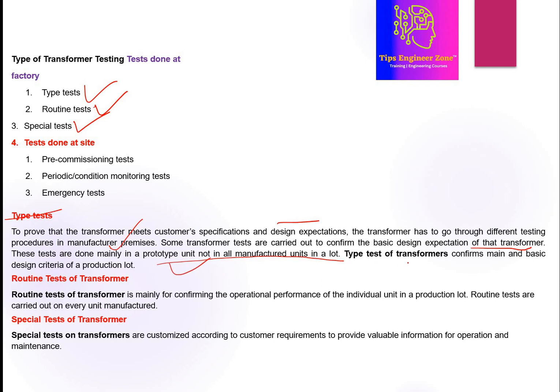A type test on a transformer confirms the main and basic design criteria of a production lot. But the routine test of a transformer is mainly for confirming the operational performance of the individual unit in a production lot, and routine tests are carried out on every manufactured unit. That means routine tests are performed on all manufactured units, but type tests are only on selected units in a lot.